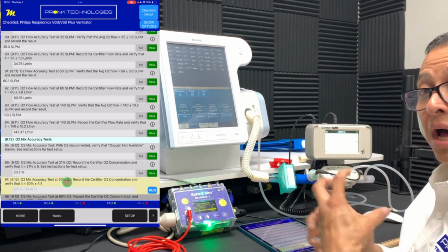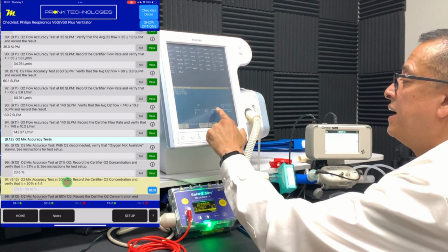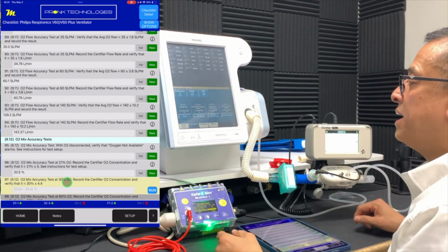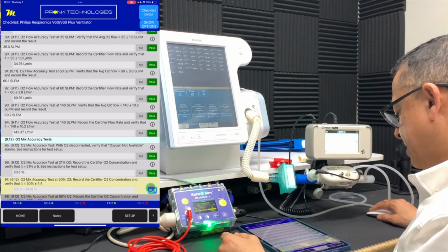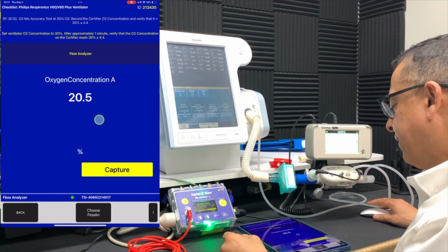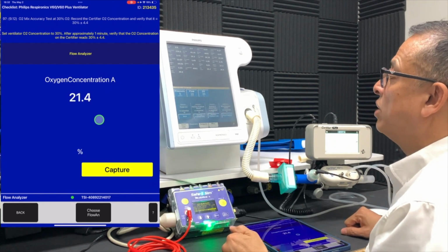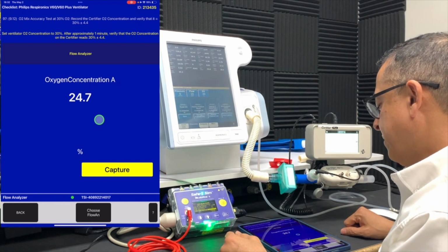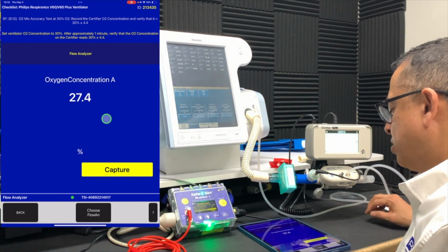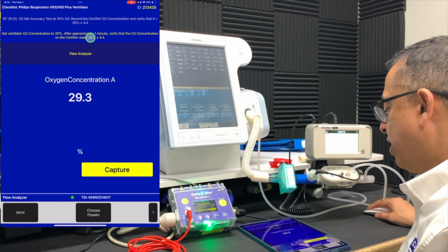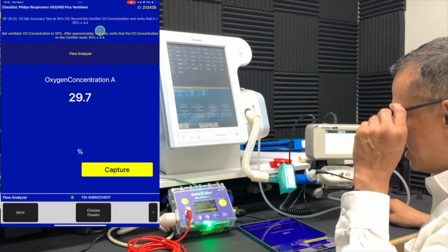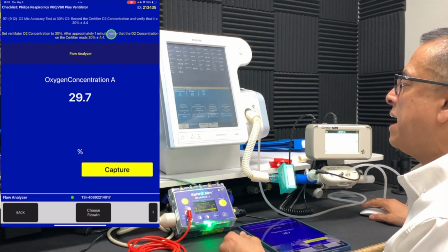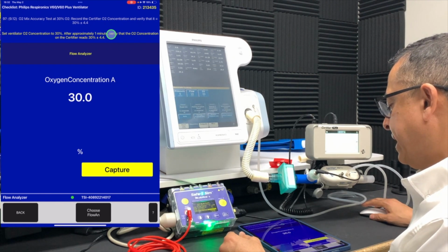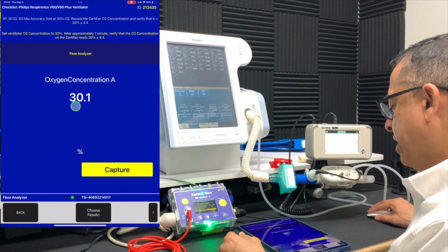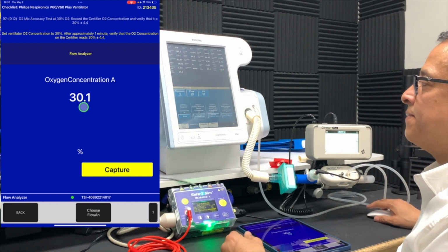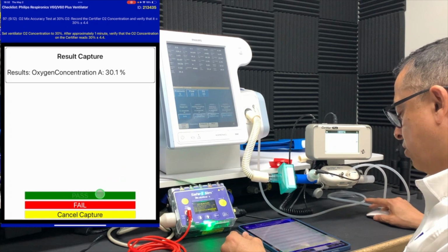Now we want to go ahead and change that oxygen mix. We want to increase that to 30% and confirm that indeed we can measure that properly. So we've set that. Now we're going to see if the certifier measures that percentage accurately or not. So we'll give it a moment for it to rise. Give it enough time to make that sample. We want to make sure that the oxygen concentration is at 30% plus or minus 4.4. So you can see it takes a couple seconds for it to sample and get us a stable measurement. And now that we've seen it, it's stabilized really right at 30.1, well within the tolerance. So we're confident with that result. Go on to the next value.